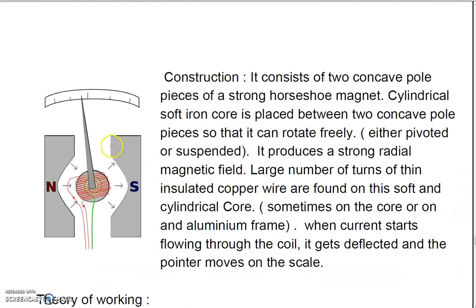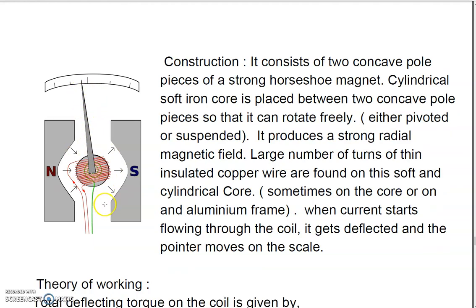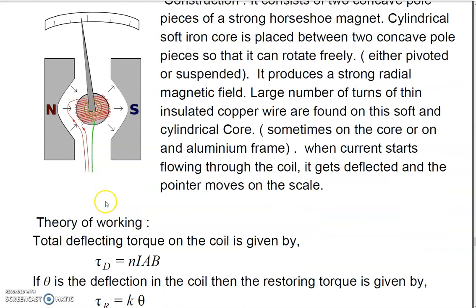To summarize the construction: two concave pole pieces of a strong horseshoe magnet, with a cylindrical soft iron core placed between them, produce a strong radial magnetic field. A large number of turns of thin insulated copper wire are wound either on the core or on an aluminum rectangular frame. Whenever current flows through the coil, it gets deflected, and the pointer attached to the coil also deflects accordingly.